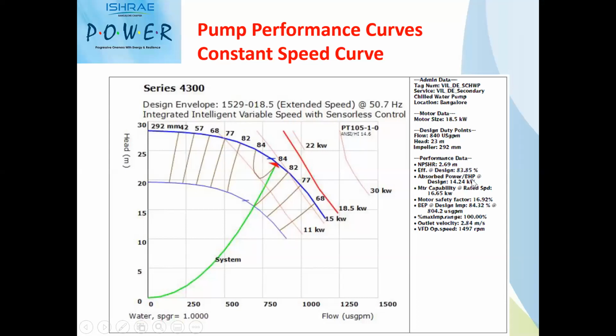the motor size. So here in this case, the absorbed power is 14.24, and any pump motor design should have, say, around 10% motor safety factor. So 14.24 into 1.1, the next available size of the motor is 18.5 kilowatts. So in this case, pump is selected based on the absorbed power, and motor is sized for 18.5 kilowatt. And then the gap between your BKW and motor power will give you the motor safety factor.